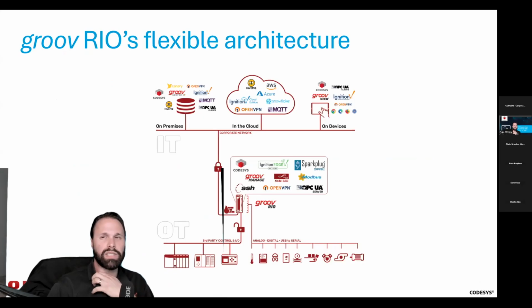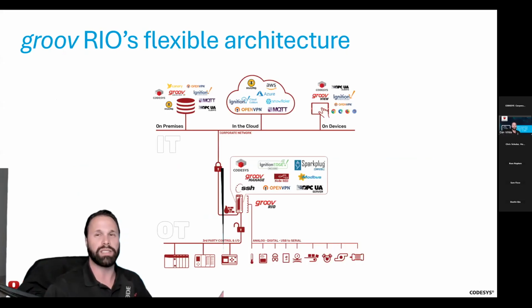One reason PEP went with groov RIO is that it isn't just a piece of I/O hardware. It sort of sits at this intersection of OT and IT. This diagram, which we show all the time, showcases that flexible architecture. Down here on the bottom, you've got your OT side where you can directly connect to field devices like physical I/O, pumps, conveyors, motors, and so on, along with PLCs and controllers through the Ethernet interface.